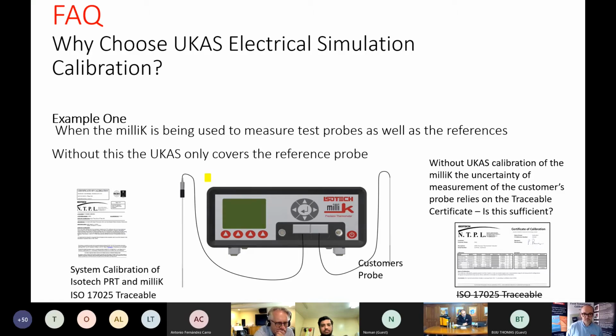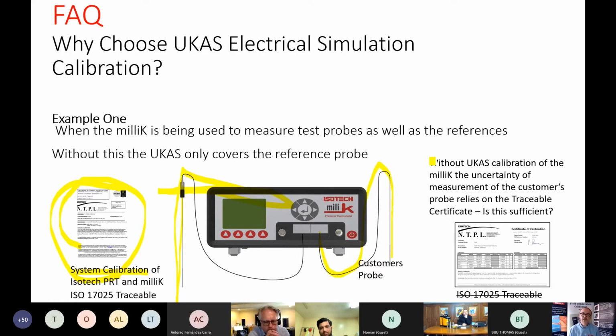So why might we need that? Well, here's one example. The milliK is being used to measure test probes as well as the references. Here's what we've been discussing, the system calibration of the thermometer and the milliK together, and this is ISO 17025. But if the customer connects their probe, which has not been to our laboratory, to the milliK, and measures the ohms or the voltage from the sensor, then it'll only have a traceable calibration certificate unless you've also chosen the UKAS option. So without UKAS calibration of the milliK, the uncertainty of measurement of the customer's probe relies on the traceable calibration certificate.